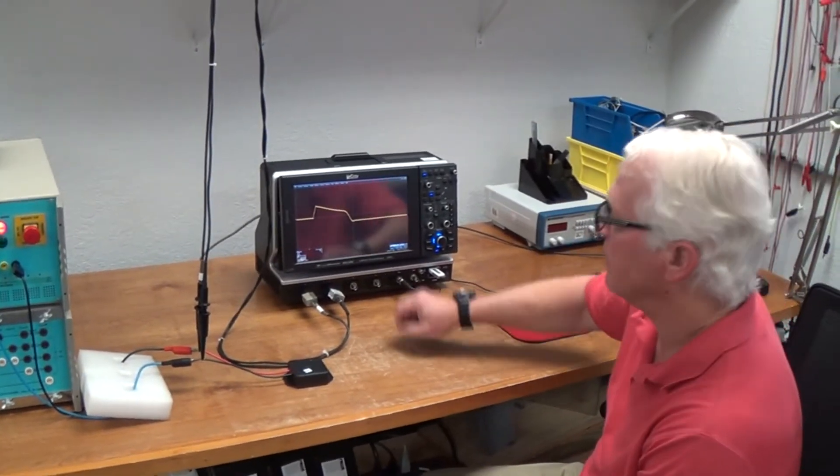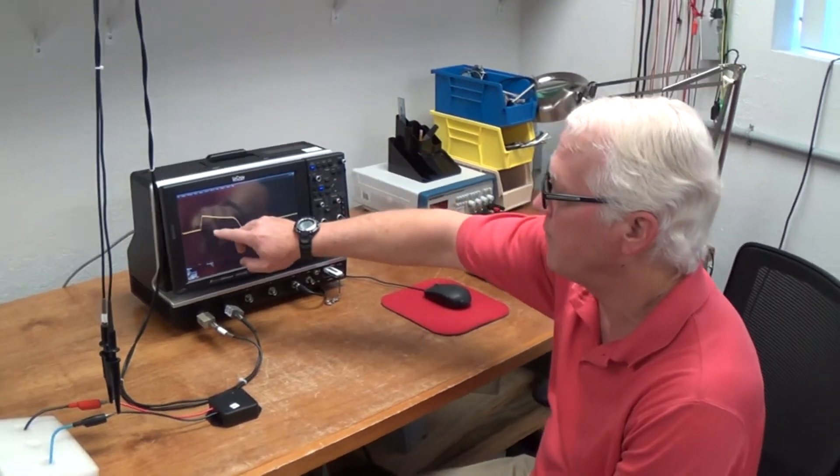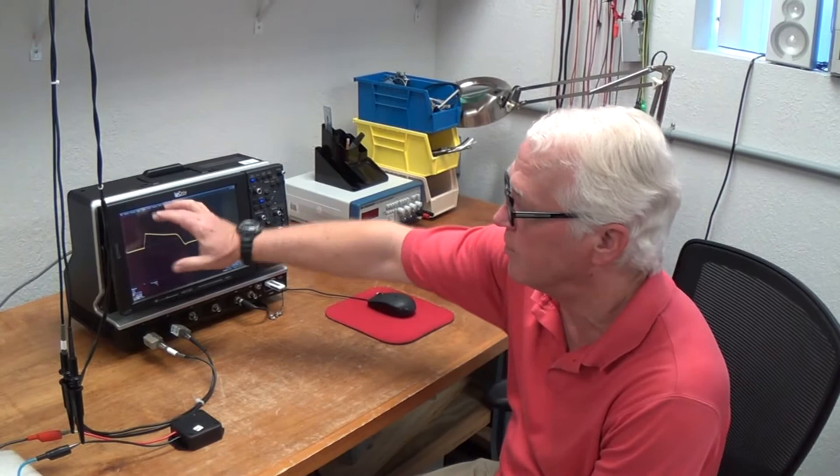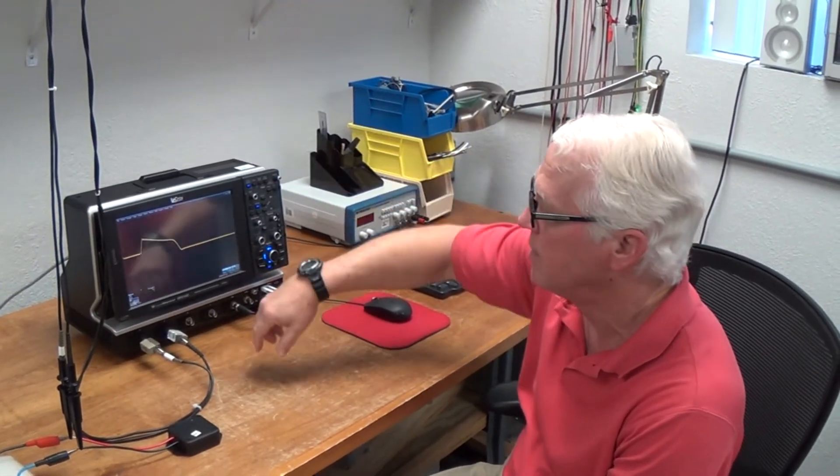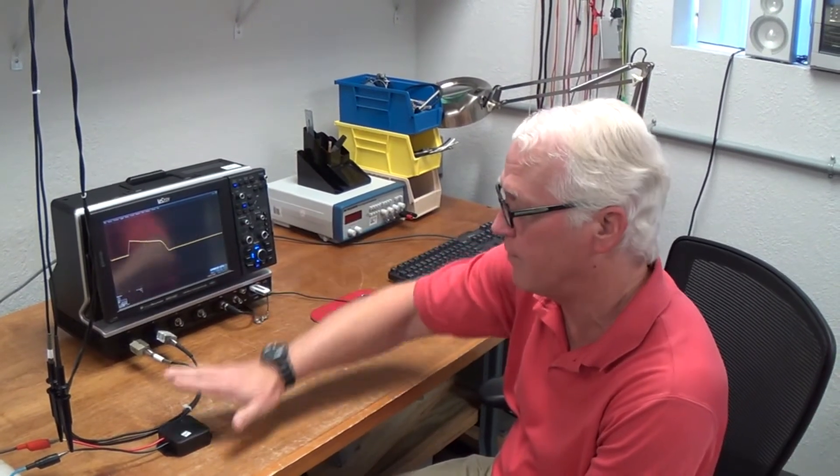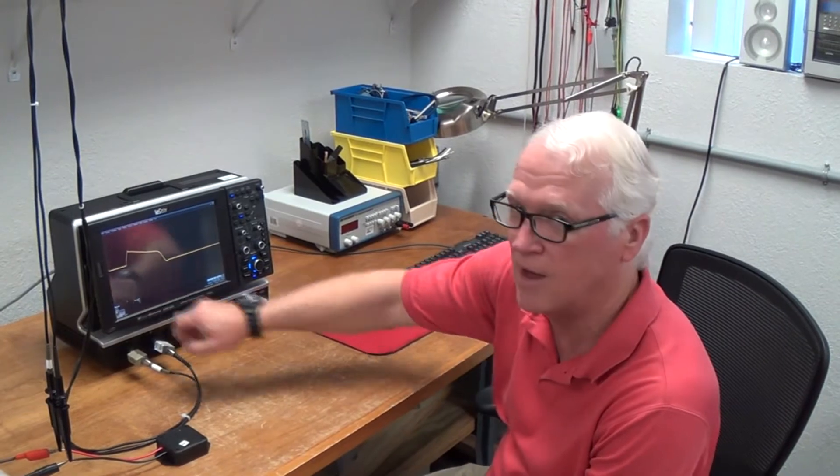Okay, I'll explain it to you. This is what's left over. They call it the let-through voltage of the surge. Now, if the surge protector hadn't been acting on this, this surge would have went all the way to 1,000 volts. But instead, it cuts it off, and so this is the part that's actually let through after the surge protector. So what's let through now is 79 volts.